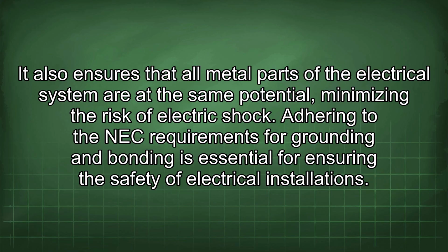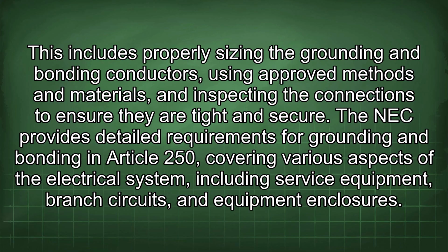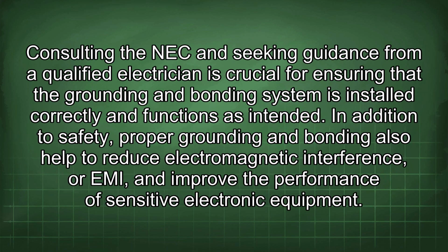Adhering to the NEC requirements for grounding and bonding is essential for ensuring the safety of electrical installations. This includes properly sizing the grounding and bonding conductors, using approved methods and materials, and inspecting the connections to ensure they are tight and secure. The NEC provides detailed requirements for grounding and bonding in Article 250, covering various aspects of the electrical system, including service equipment, branch circuits, and equipment enclosures. Consulting the NEC and seeking guidance from a qualified electrician is crucial for ensuring that the grounding and bonding system is installed correctly and functions as intended.